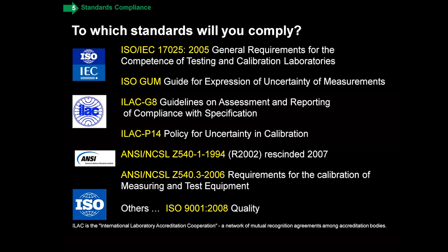The question for this module is: what standards do you want to comply with? Probably the most important calibration standard for calibration laboratories is 17025, and you can get an idea of its importance just from the title: General Requirements for the Competence of Testing and Calibration Laboratories. Very important as part of the interpretation and implementation of 17025 is the ISO-GUM, which was covered in module three.